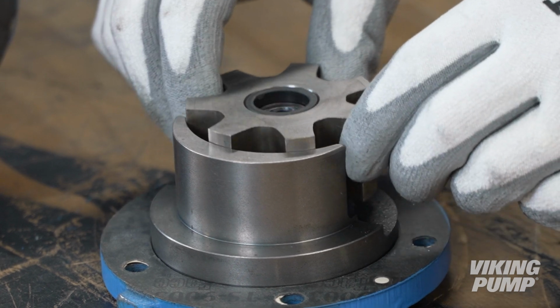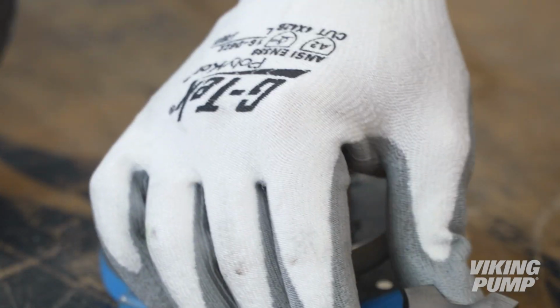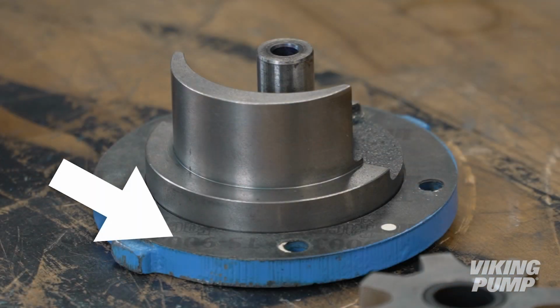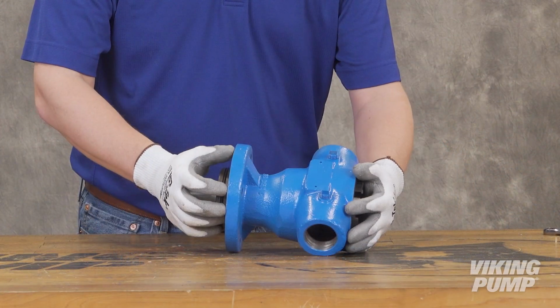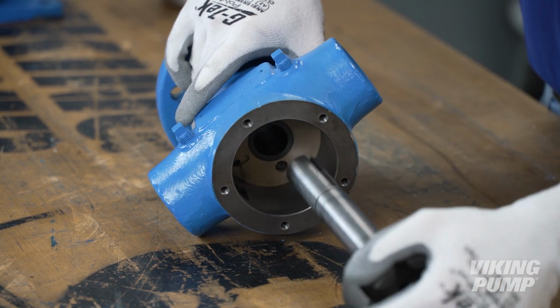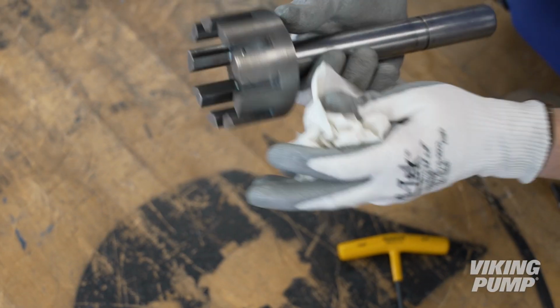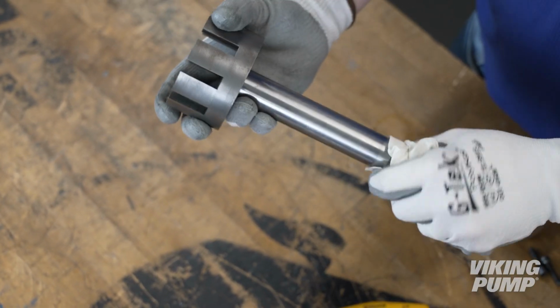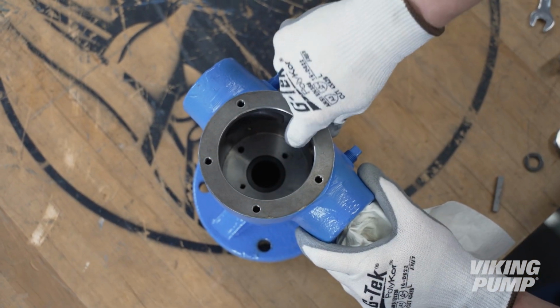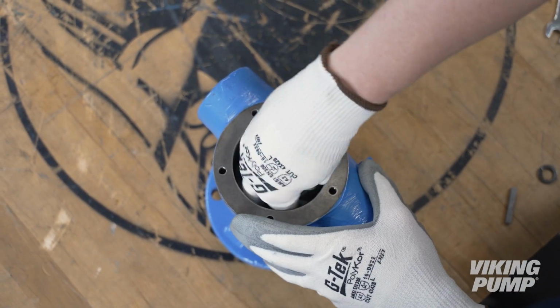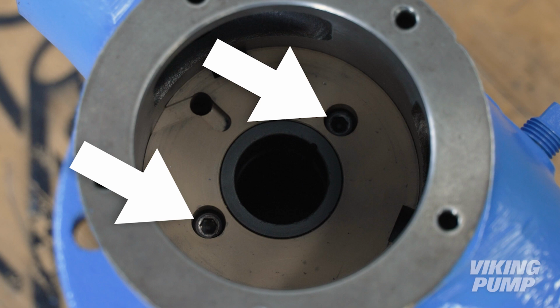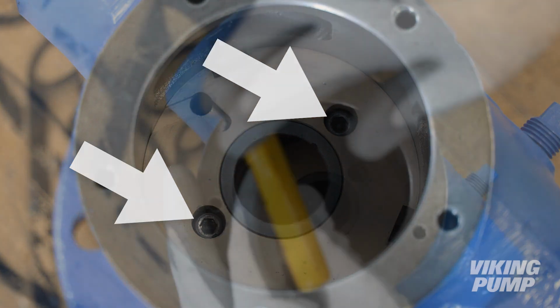Remove the idler gear from the idler pin. Make sure to keep the head gaskets, as they are all required to maintain the proper end clearance. Remove the rotor shaft assembly. Inspect the pump parts for wear and replace any worn components. If a new casing or balance plate bushings are required, it's suggested to remove the balance plate by removing the 2 cap screws.